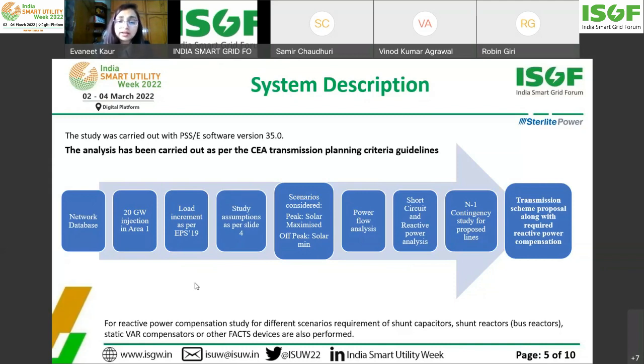Along with the power flow analysis, short circuit analysis and reactive power compensation study are also performed for different scenarios to validate the size and requirement of compensation devices. N-1 contingency study is also done for the proposed transmission line as per CEA transmission planning guidelines. After that, the transmission scheme is proposed along with the required reactive power compensation.